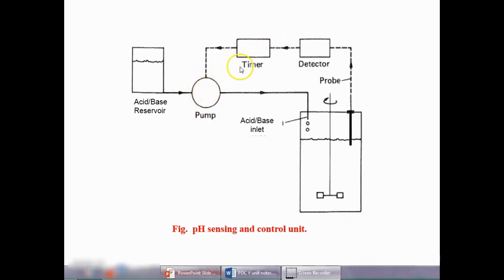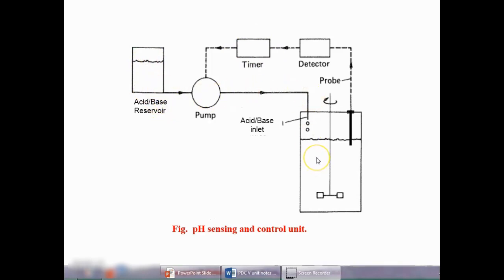The pump will start for a predetermined time — the addition cycle will be around 0 to 5 seconds. In those 0 to 5 seconds, either acid or base will come from the reservoir through the pump into the fermentation tank. For 5 seconds, this acid or base will be added to the fermentation process.